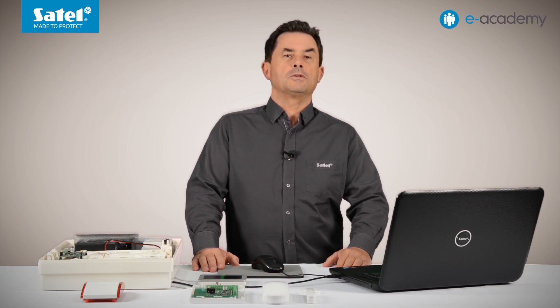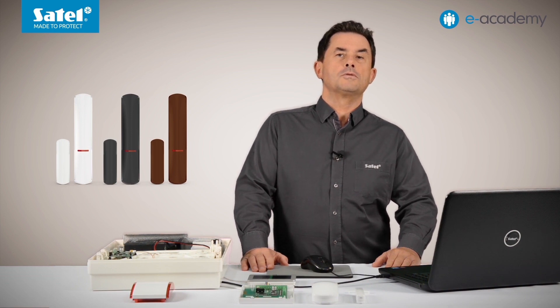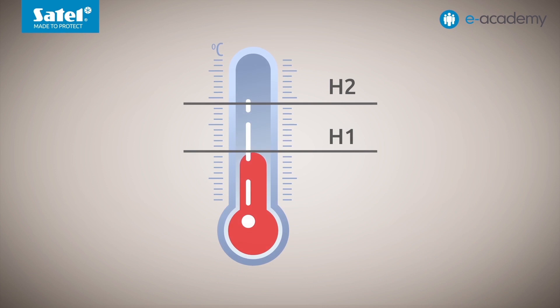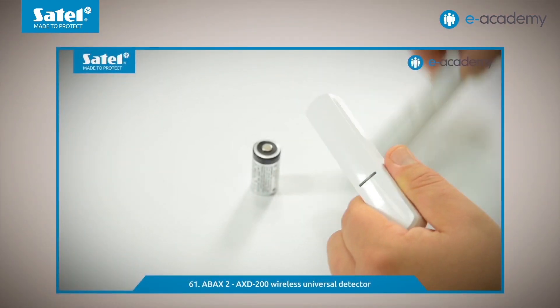Besides ATD-200, the AXD200 wireless multipurpose detector is another device working within the ABAX2 system that can act as a temperature detector. The AXD200 detector has one advantage over the ATD-200: we can program two thresholds. For example, when the first temperature threshold is exceeded, the control panel can activate the chosen output, whereas when the second threshold is exceeded, the alarm can be triggered. We talked more extensively about the AXD200 detector in episode 61.